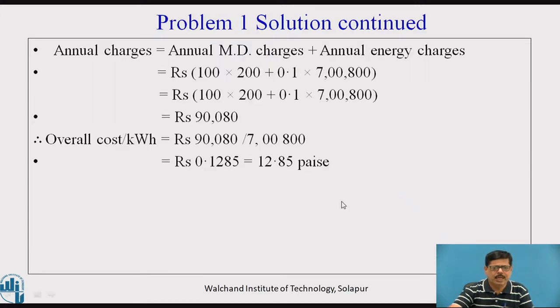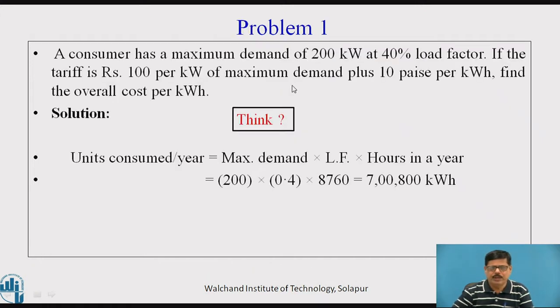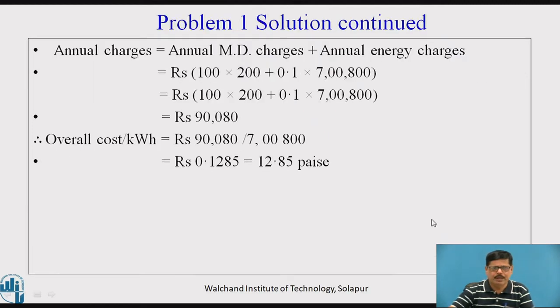We can calculate the annual charges using the given tariff. The annual maximum demand charges will be Rs. 100 per kW of maximum demand into 200 kW, plus 0.1 rupees into total number of units generated. So the annual charges come out to be Rs. 90,080. When we divide by the total number of units generated, that is 7,00,800, we get the overall cost per unit of electrical energy as Rs. 0.1285, that is 12.85 paise.